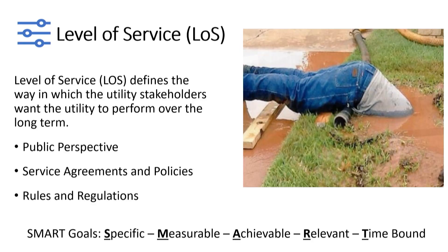There's also whatever you're putting in your service agreements and policies — what are you saying to customers you're going to provide? And there's a level of service expected by rules and regulations from federal, state, and even local levels. For example, pressure requirements have a minimum, chlorine residuals have a minimum. This is the driver of making sure what we're doing and how we're doing it — why it's important to manage and maintain pumps, tanks, and staff, to make sure our level of service continues as it's supposed to.